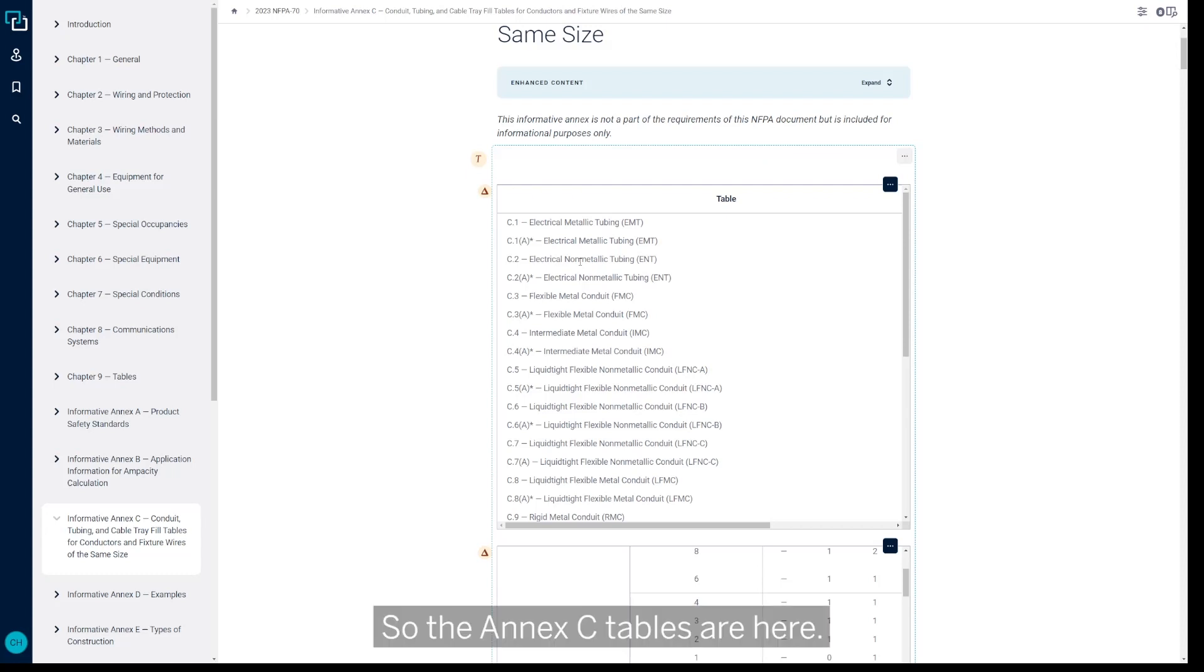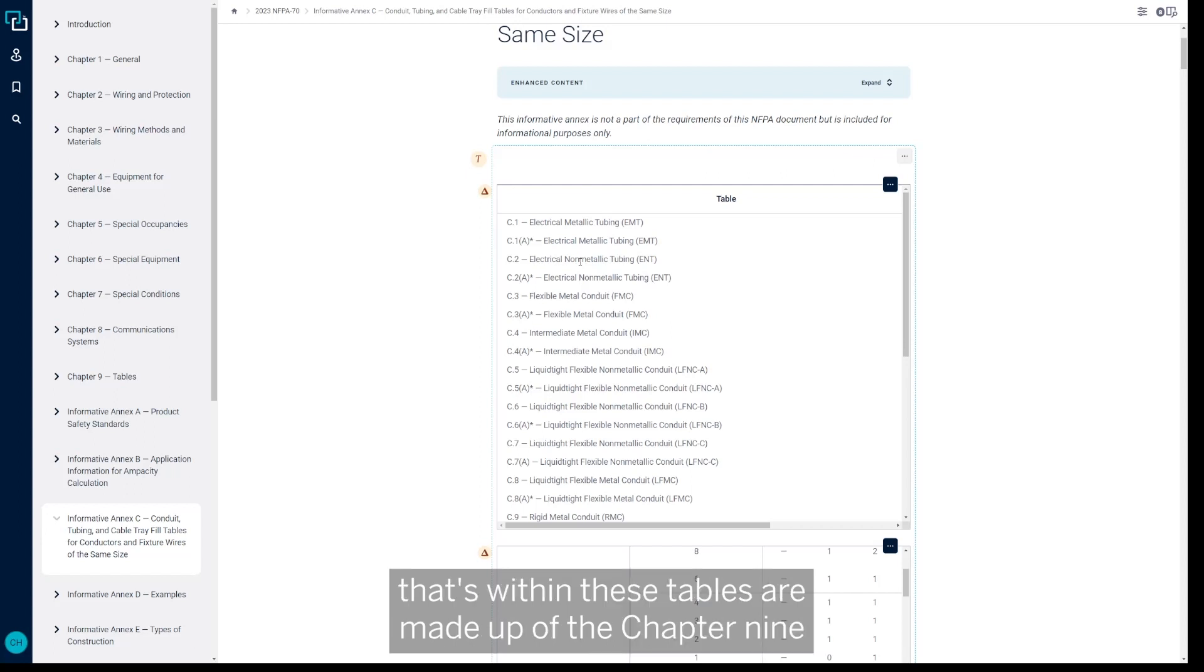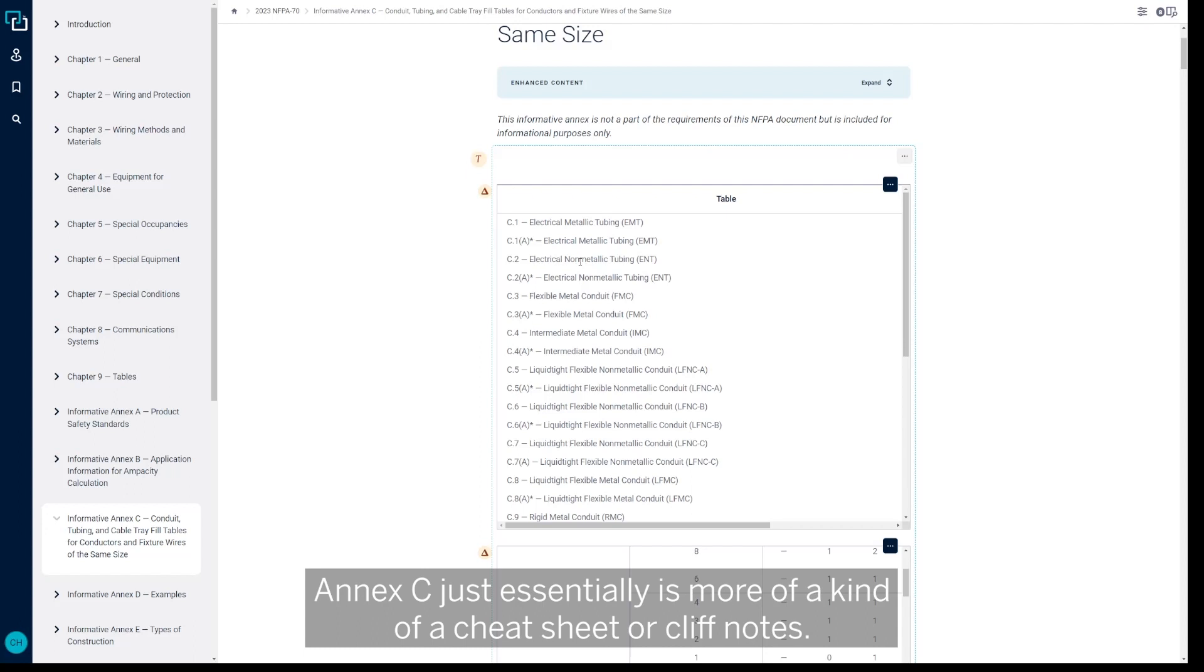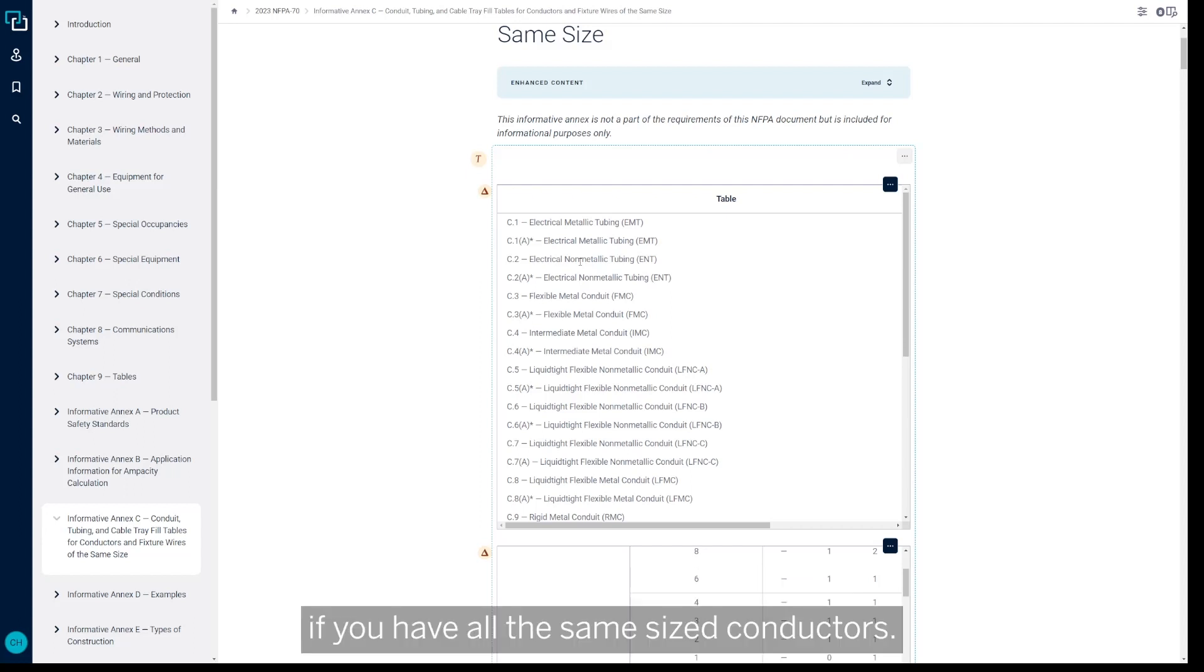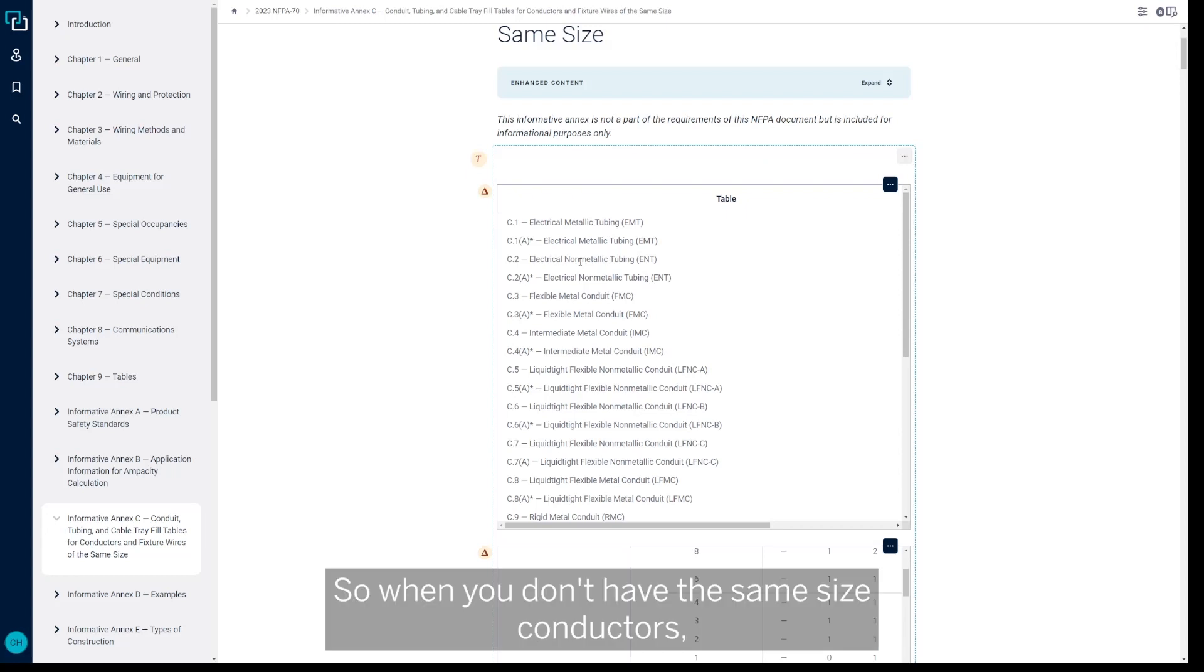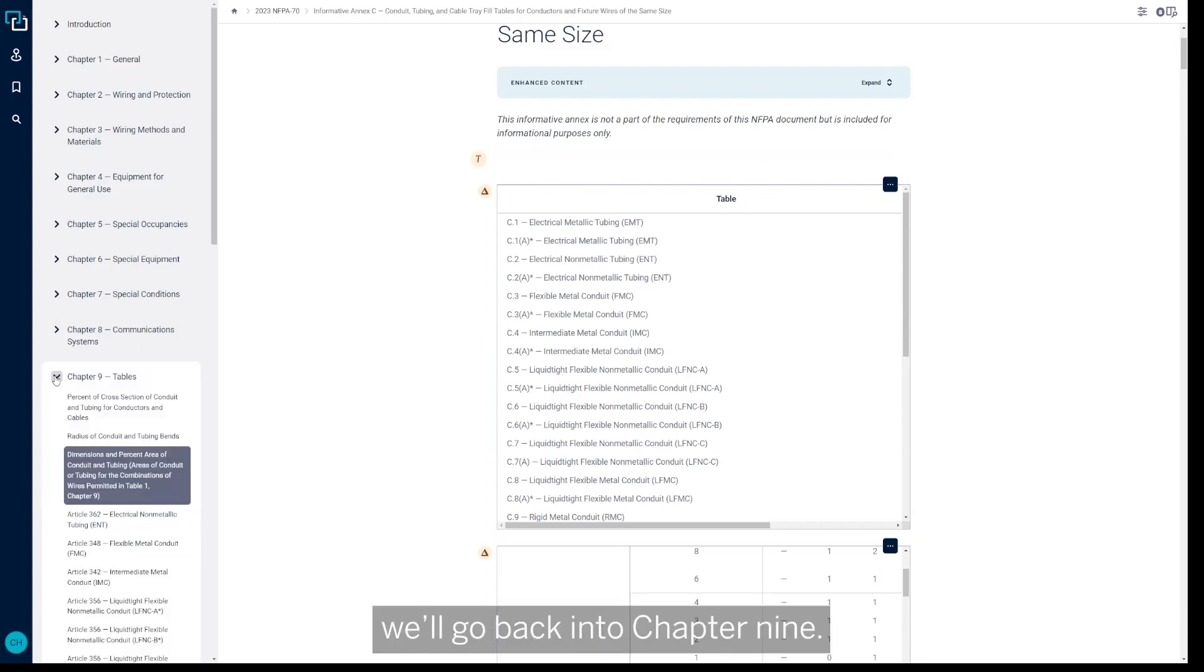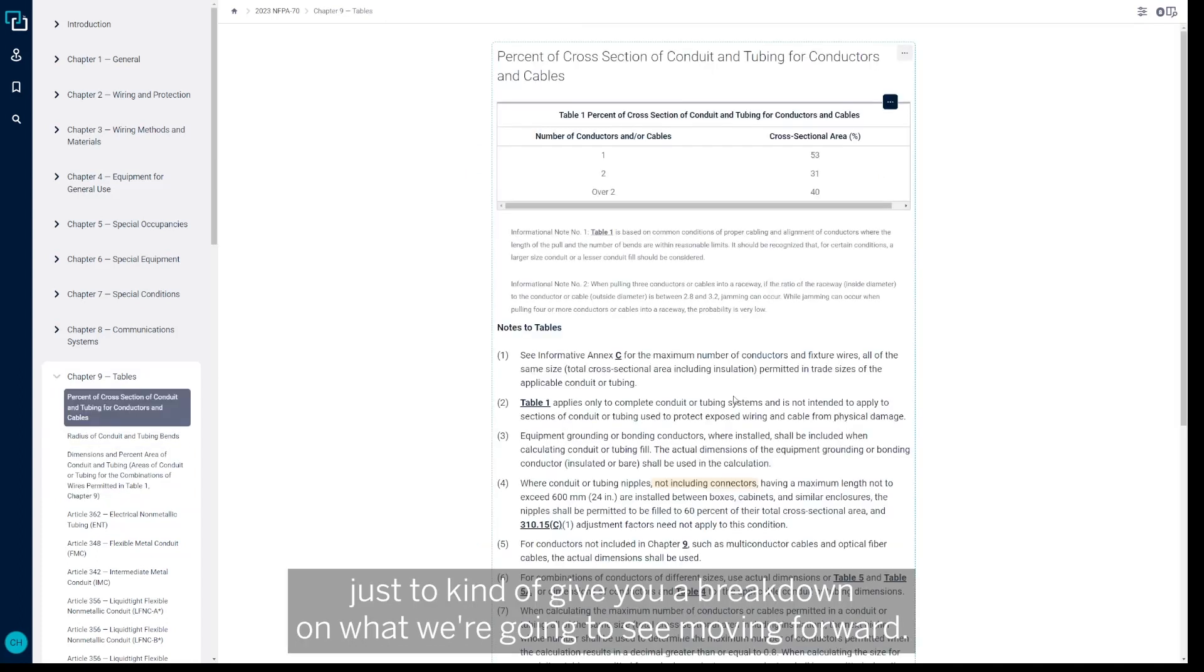So the Annex C tables are here, they're great to utilize if you have the same size conductor. And these tables—the information that's within these tables—are made up of the Chapter 9 tables that we're about to look at. Annex C just essentially is more of a kind of a cheat sheet or cliff notes, so you don't have to go back and utilize the Chapter 9 tables if you have all the same size conductors. So when you don't have the same size conductors, we're going back into Chapter 9.